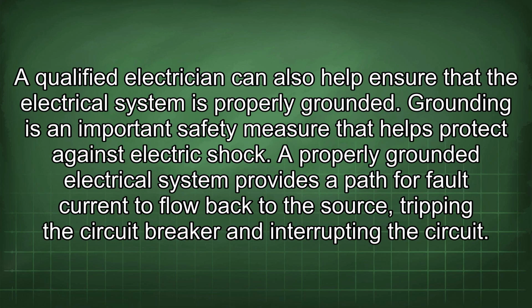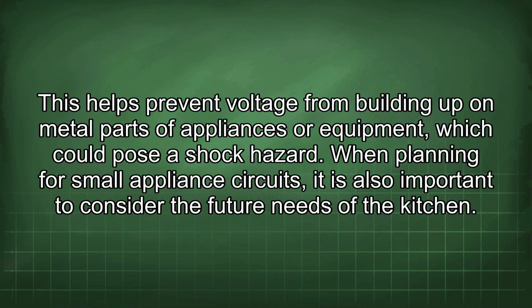A qualified electrician can also help ensure that the electrical system is properly grounded. Grounding is an important safety measure that helps protect against electric shock. A properly grounded electrical system provides a path for fault current to flow back to the source, tripping the circuit breaker and interrupting the circuit. This helps prevent voltage from building up on metal parts of appliances or equipment, which could pose a shock hazard.